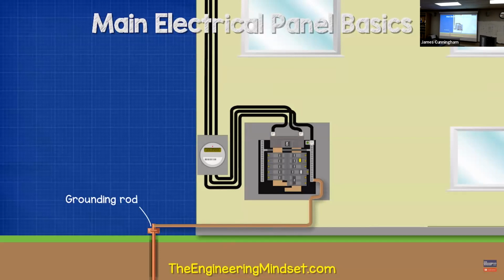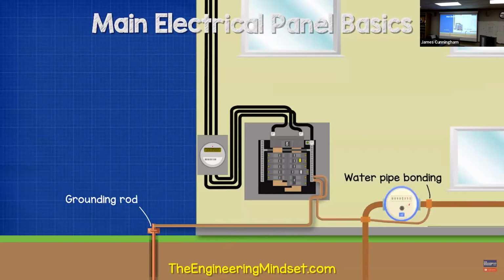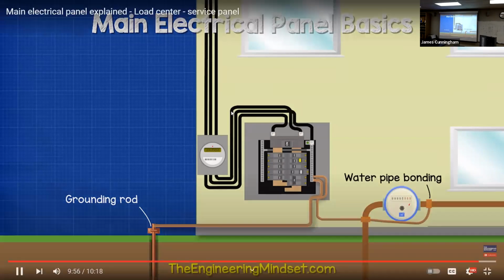Under normal circumstances, no electrical current will flow through this wire. Its purpose is to dissipate high static voltages from things like lightning. This way, the electrical systems and equipment are protected from damage. Additionally, we'll also find a bonding wire to metal pipework in the property. This is to provide a safe route for electricity to flow should a hot wire come into contact with a metal pipe, and this way it will prevent a person being electrocuted if they were to touch the pipework.